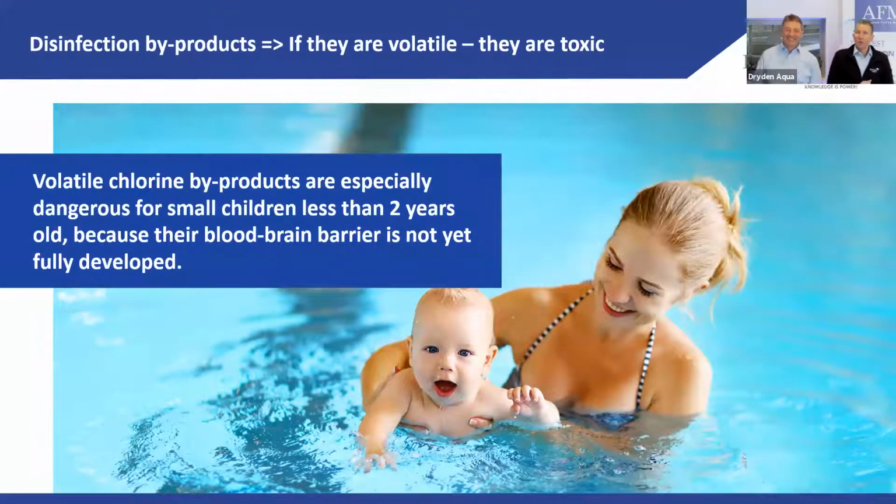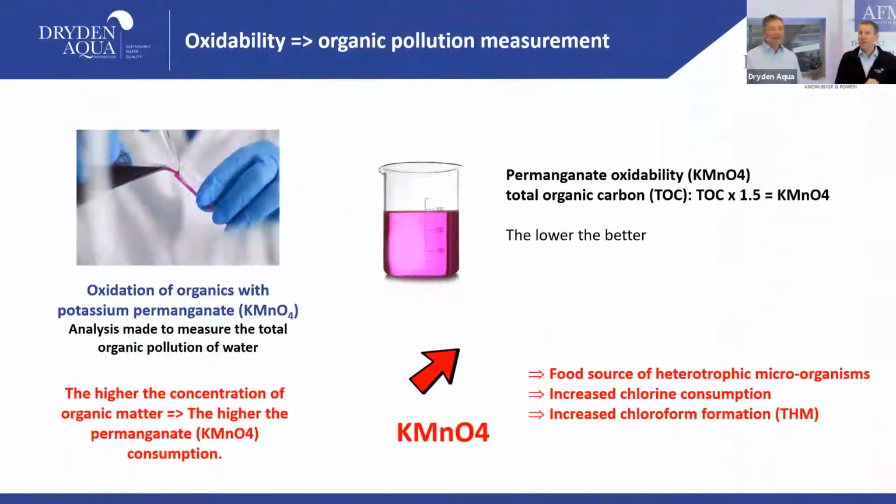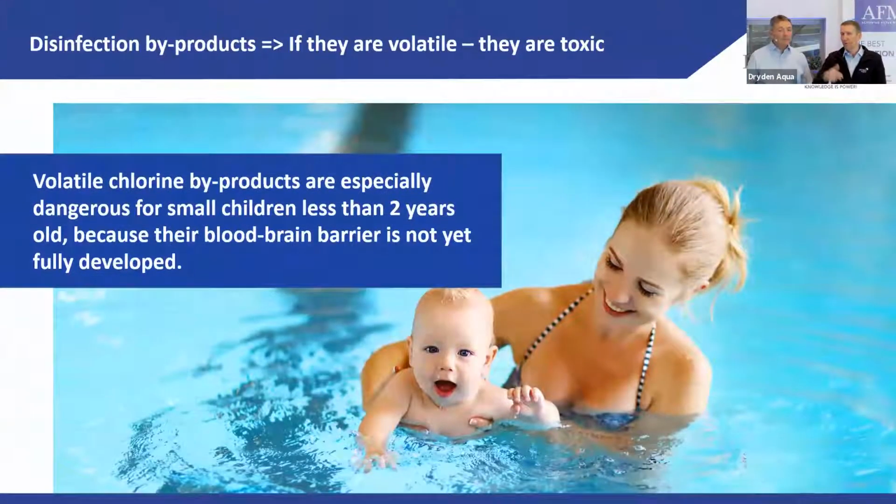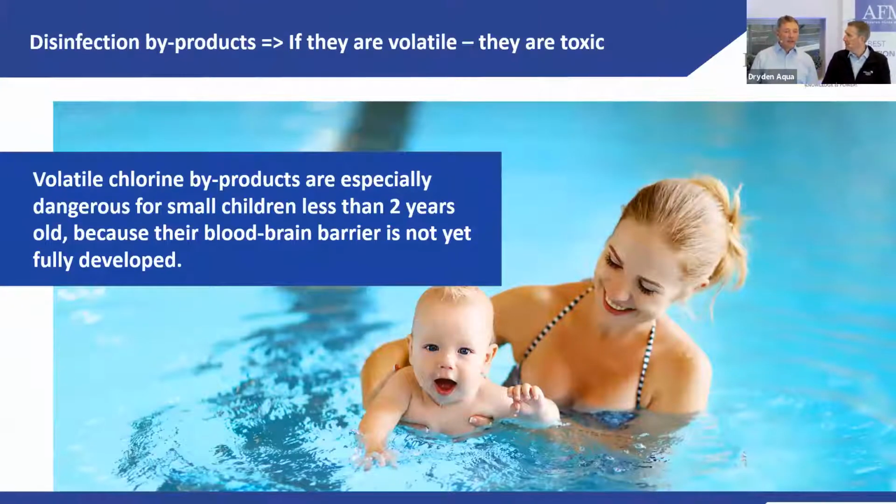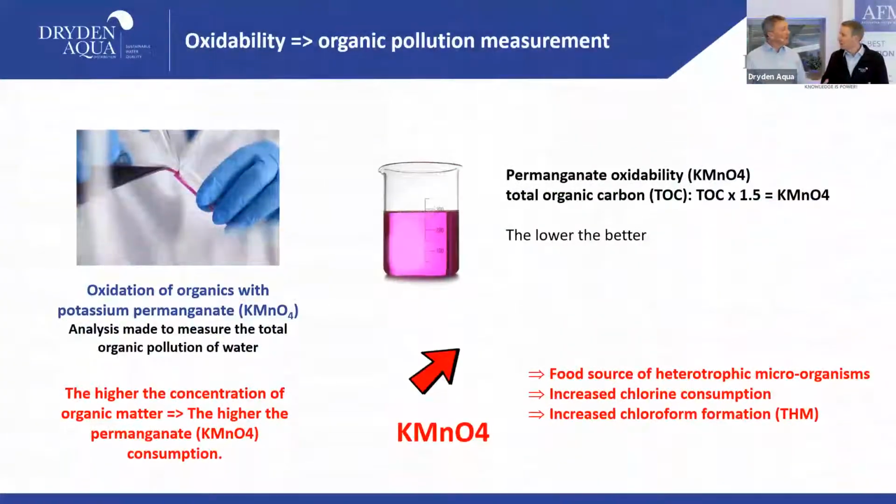So you mentioned that the amount of organic pollution is very important, right? Yes, exactly. There is a way to measure this. Yes, there are 2 ways, KMnO4 or TOC. KMnO4 measures the oxidability of the water. That means how much organics there are.